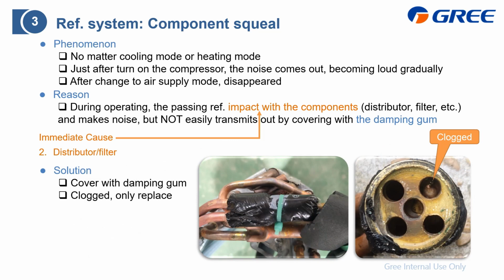As we already know the reason why this noise comes out, the solution is also very easy. We cannot stop this refrigerant flow, as you will be doing the cooling or heating. What we can do is just to cover or lower this noise. So the first solution is just to cover it with the damping gum, just like this. The other case is maybe this distributor or this filter is clogged, just like this one. You can find it is clogged, and this also makes the noise. So the solution for this one is just to replace this distributor.